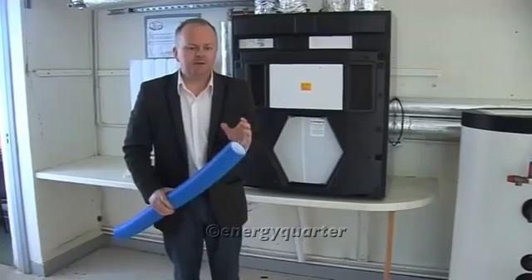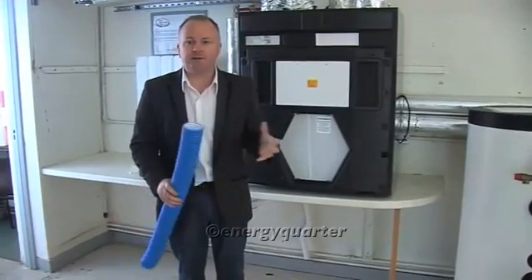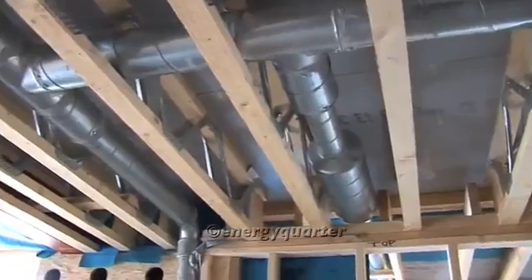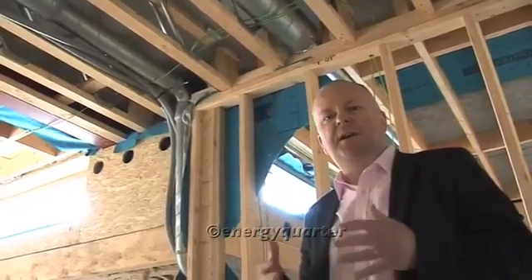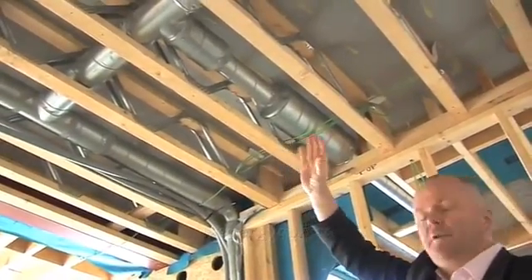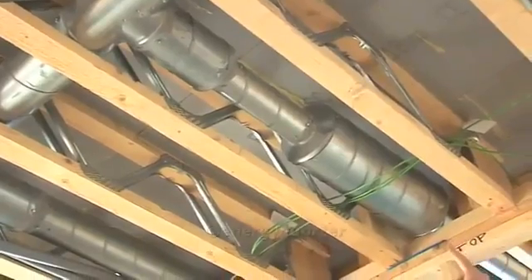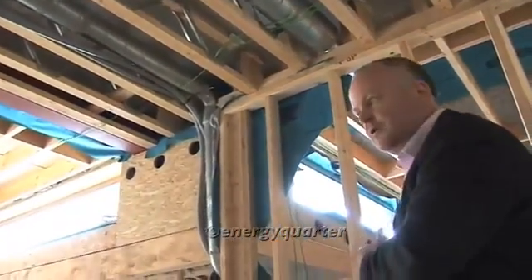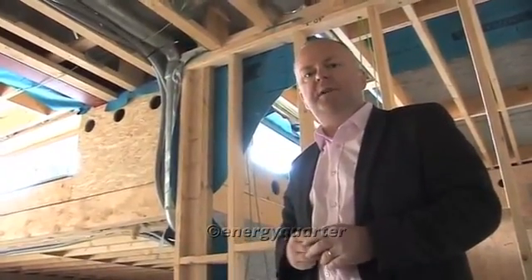Sticking with the lung analogy, it's important to make a good selection of ductwork. On a site visit we saw a fantastic example of high-quality ducting used in a passive house. Here we're going from a main trunk of around 150mm diameter down to a smaller 100mm pipe. The fat piece of duct you see is called a sound attenuator, and its main function is to stop crosstalk between a bedroom and the living space — a very important part of ventilation system design.